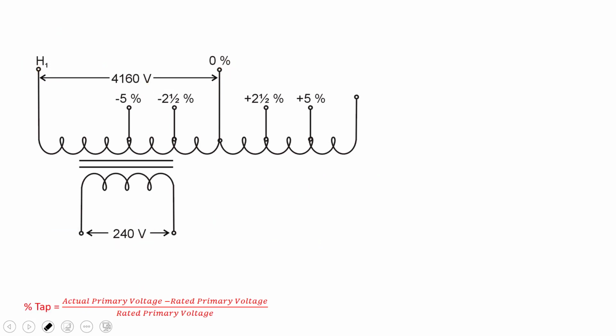So let's take the concepts that we have already learned with the taps on a transformer. So, volts per turn. If I have the full 4160 up here and it's on the 0% tap, I'm going to establish the correct volts per turn that I need for the secondary. Now if the voltage is low, like it was before, 3,952 volts, and I still have the same number of turns, then my volts per turn is going to go down, and it will also go down on the secondary. So I will no longer get my 240. I'll get that 228 or whatever it was. So what can we do? Well, we can de-energize the transformer, and we can terminate it on a lower percent tap. What does that really mean?